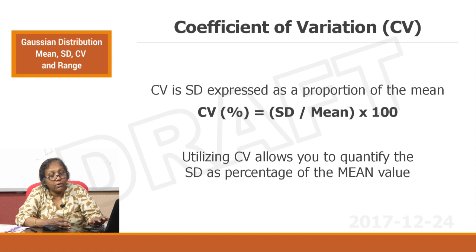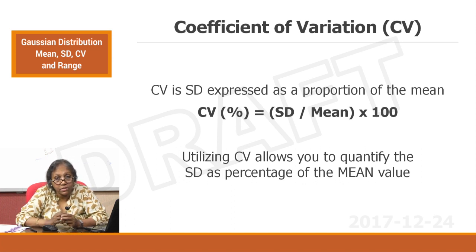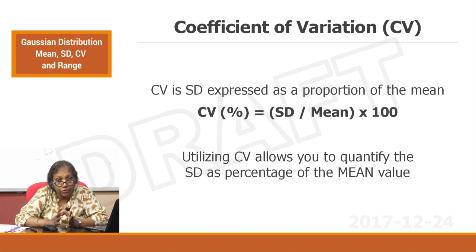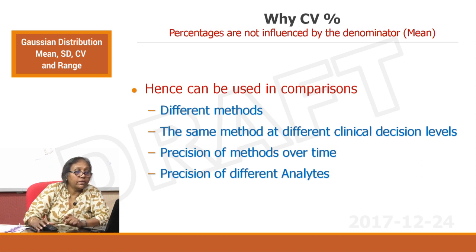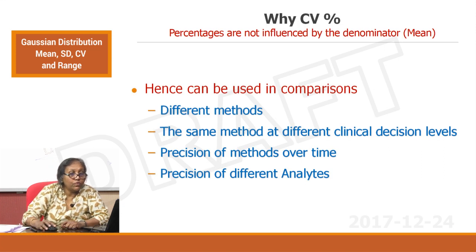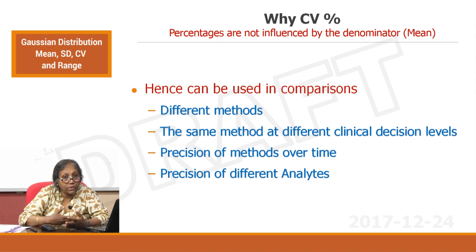CV% is a great equalizer and is always used for comparison to understand how the performance of a machine or analytical system is. CV can be used for comparisons of different methods, the same method at different clinical decision levels — yes, you have Level 1 QC, Level 2, Level 3 QC — and you can analyze performance at different decision levels.